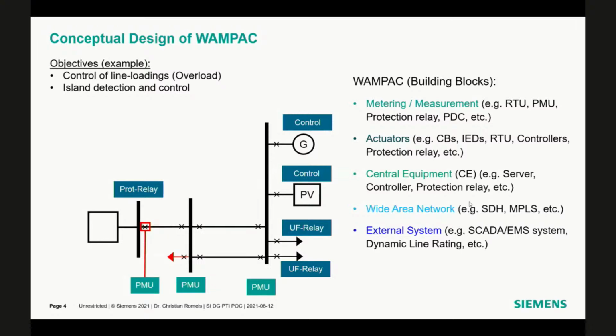Maybe you can say, okay, if I expand my system with information from PMUs, I also can say, okay, with a central equipment like a server and controller or protection relay, I can block or enable the under frequency load shedding, or change the feeders I want to shed based on the actual active power.